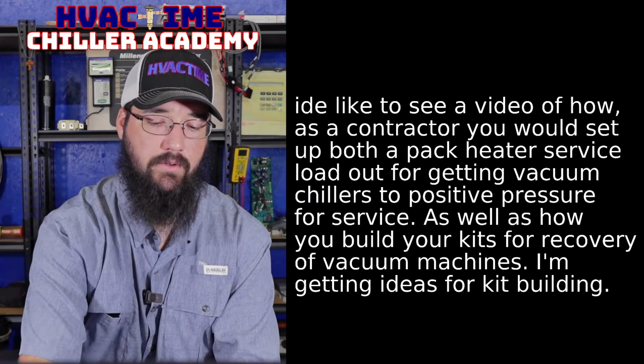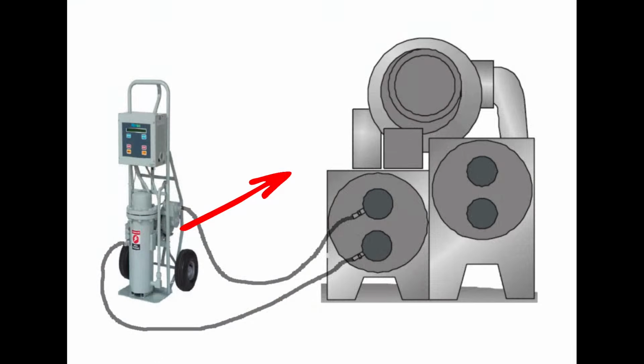So let's talk about the pressurizer first. To show you, this is the one that I personally prefer and like to use. So you've got the actual pressurizer unit here. It's just going to connect. Now, they actually recommend connecting this on the evaporator. Typically, when I've done this, I've always gone through the condenser, but the point of being able to do it in the evaporator instead is you're actually putting that heat to the liquid refrigerant, because on a machine like this with the low pressure, you're dealing with a flooded or hybrid falling film barrel, and ultimately all of your refrigerant at idle, your liquid refrigerant specifically, is going to be stacked in the evaporator. So the whole point of doing it on the evaporator side is we're getting that actual liquid refrigerant heated up.